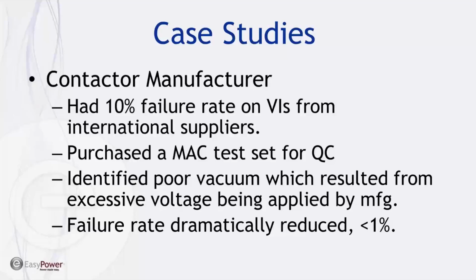In talking with their manufacturer, they determined that one of the conditioning processes that they were doing on these vacuum interrupters after they were manufactured was doing damage to the inside of the vacuum interrupter and causing an accelerated leak rate inside. So after this was determined and the problem was corrected, they purchased another MAC test set from us and sent it to their manufacturer to be tested before they shipped the VIs. And so in that time, the failure rate of their contactors has dropped dramatically, and last I heard it was less than 1%, but it could be much better.